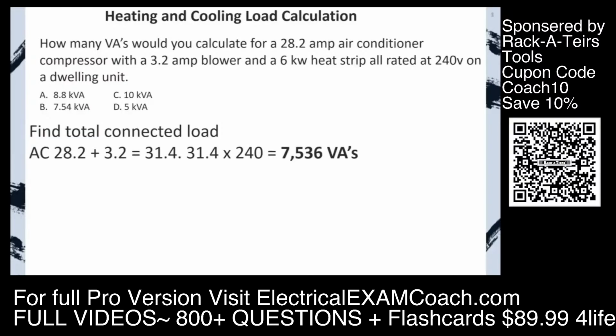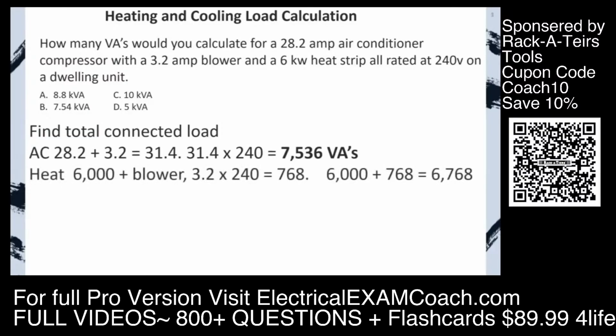Now let's do our heat. We know that we had 6 kW to start with. Then we need to add our blower motor. We take our blower motor at 3.2 multiplied by the voltage, and that gives us another 768 VAs.